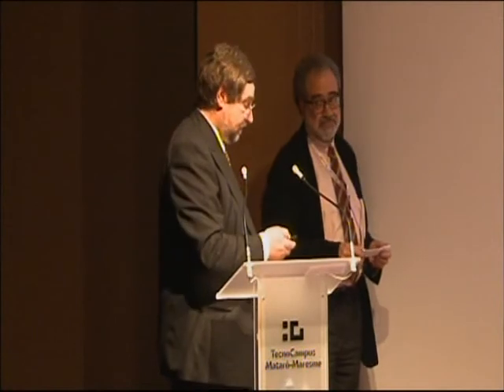Behavior at pollutant peaks is still working well. Investment cost is not really expensive. The regulation action is still good. The additive supply cost is still higher. You saw that bicarbonate is much more expensive, but the residue disposal costs are still okay, and the operating costs are also less. And in addition, energy efficiency for the FGD is also a really big plus because we put out 2 to 5 megawatts from each line.